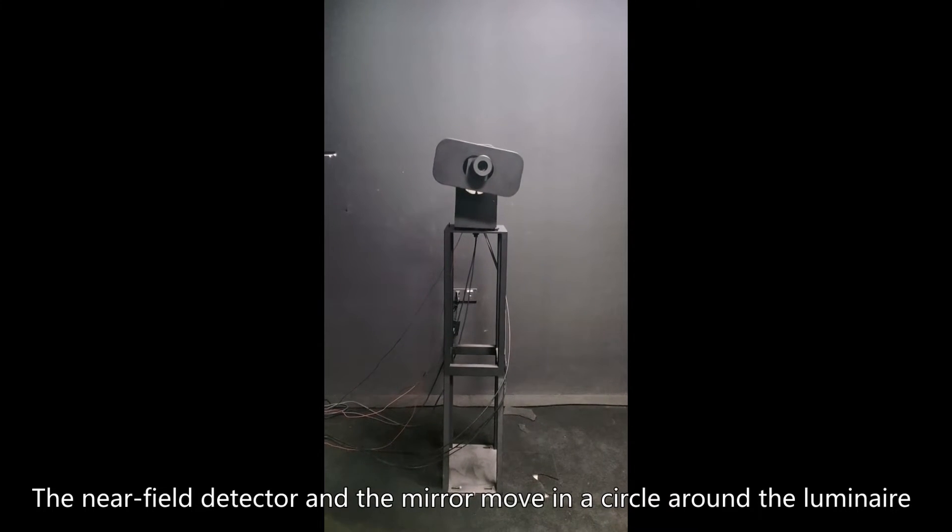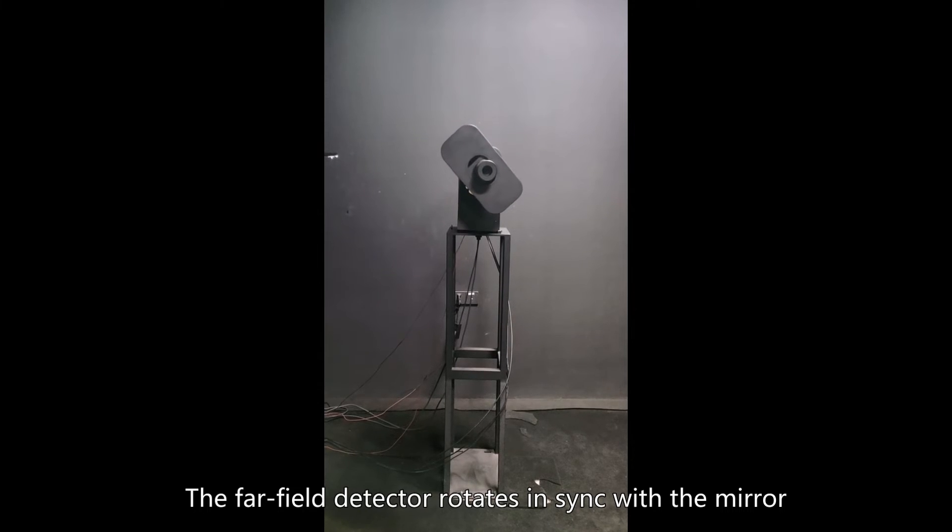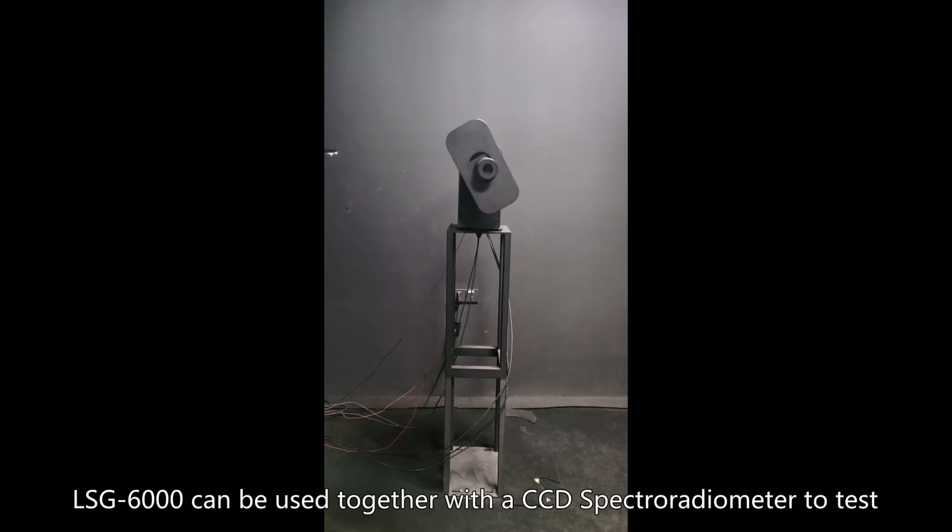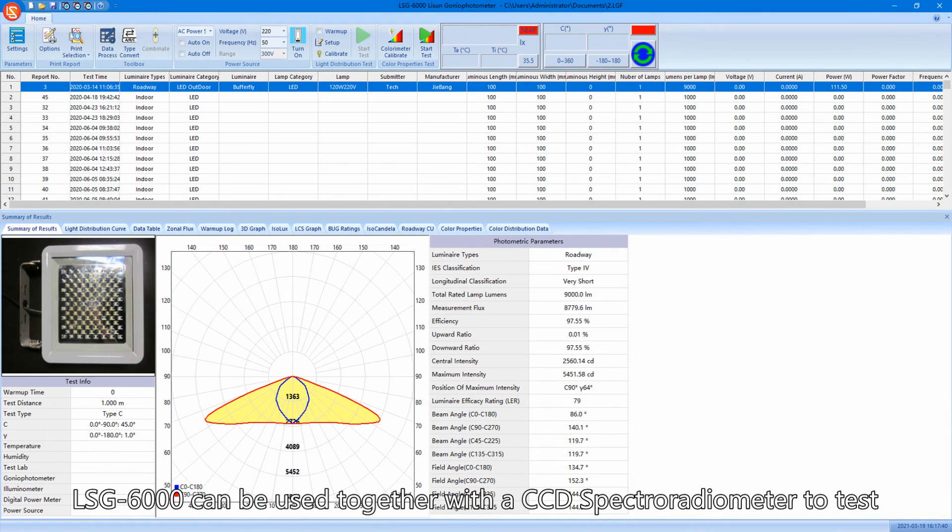The far field detector rotates in sync with the mirror. LSG-6000 can be used together with a CCD spectroradiometer to test spatial CCT distribution and other spectral color parameters.